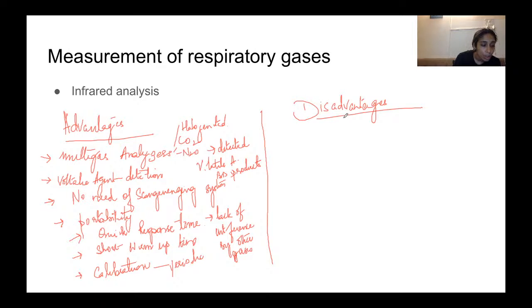Okay, now what are the disadvantages? Oxygen is not absorbed by infrared light. It causes broadening of the carbon dioxide, so when oxygen is being given, oxygen can decrease the carbon dioxide curve. Then there is some overlap of carbon dioxide and nitrous oxide infrared absorption, so there can be some erroneous readings from the overlap in the carbon dioxide and nitrous oxide readings.